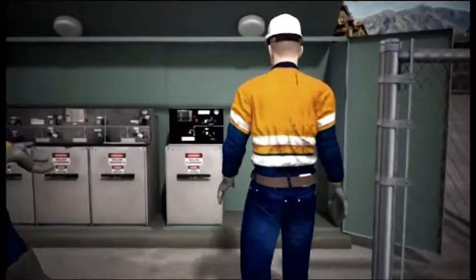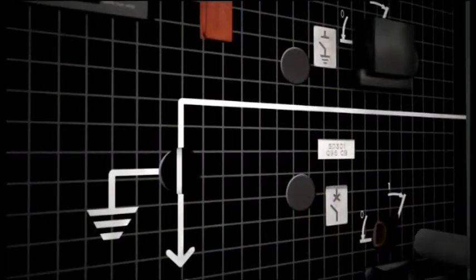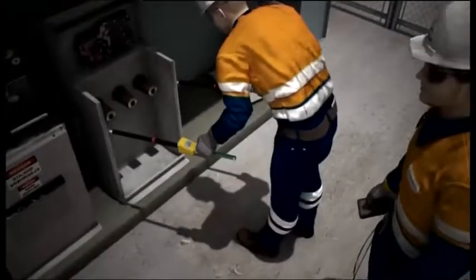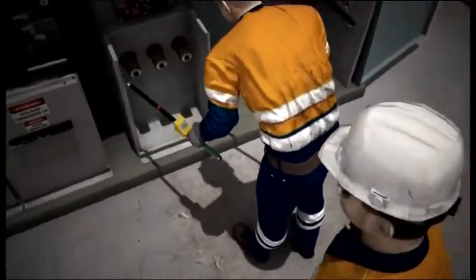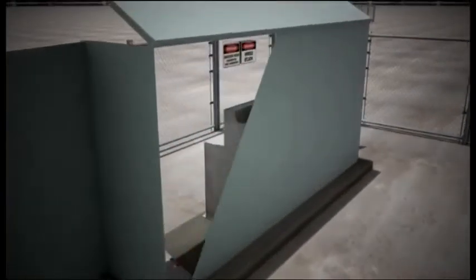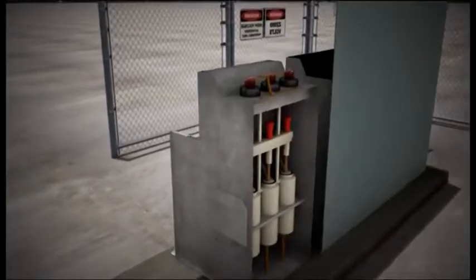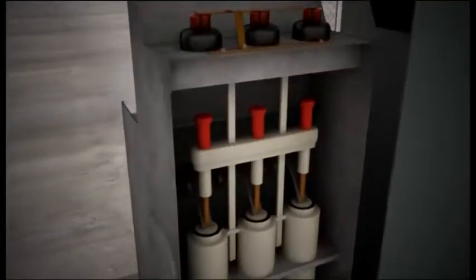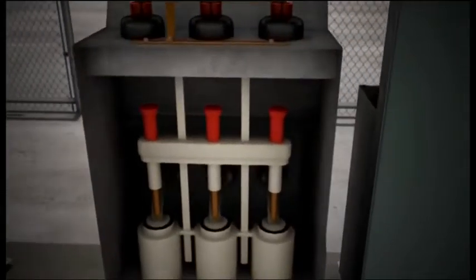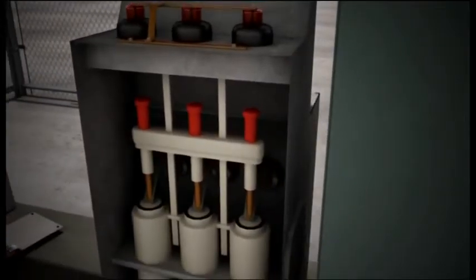But how did this happen? Dave was convinced that he de-energized the unit when he turned the crank handle to open, and Andrew had tested it for dead just minutes before. If we go back and view the high voltage unit from the inside, we can see exactly what went wrong and what contributed to this accident occurring.